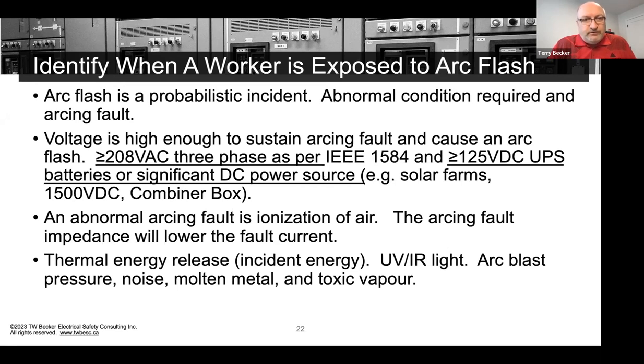So large solar farms, if you weren't aware, combine the photovoltaic cells or panels into 1500 volt DC combiner boxes, and then take the 1500 volts DC and invert it and step it up to high voltage distribution and transmission. So for DC, those are the nominal volts of concern: significant power source output, UPS batteries, or as I just mentioned, the solar.